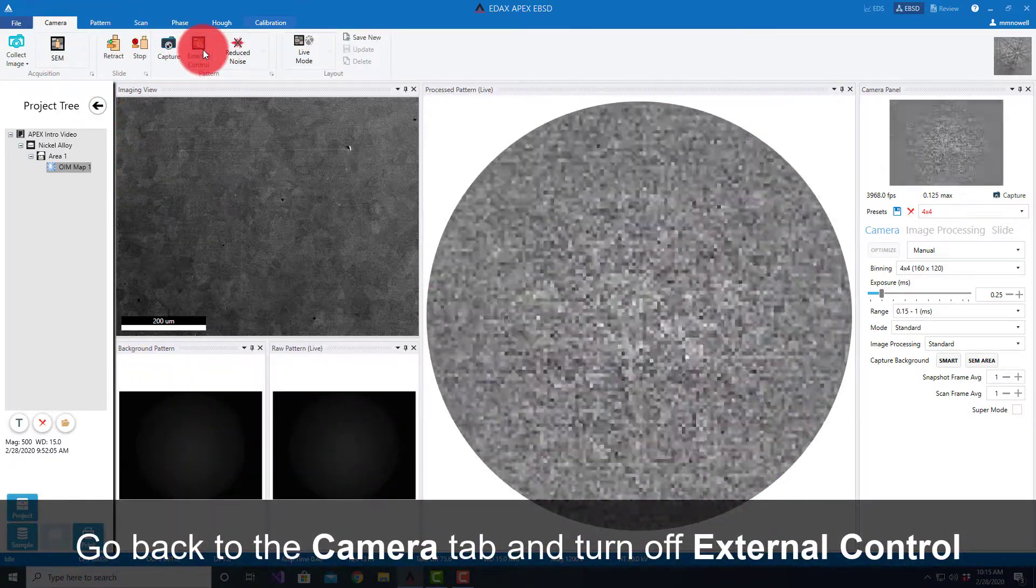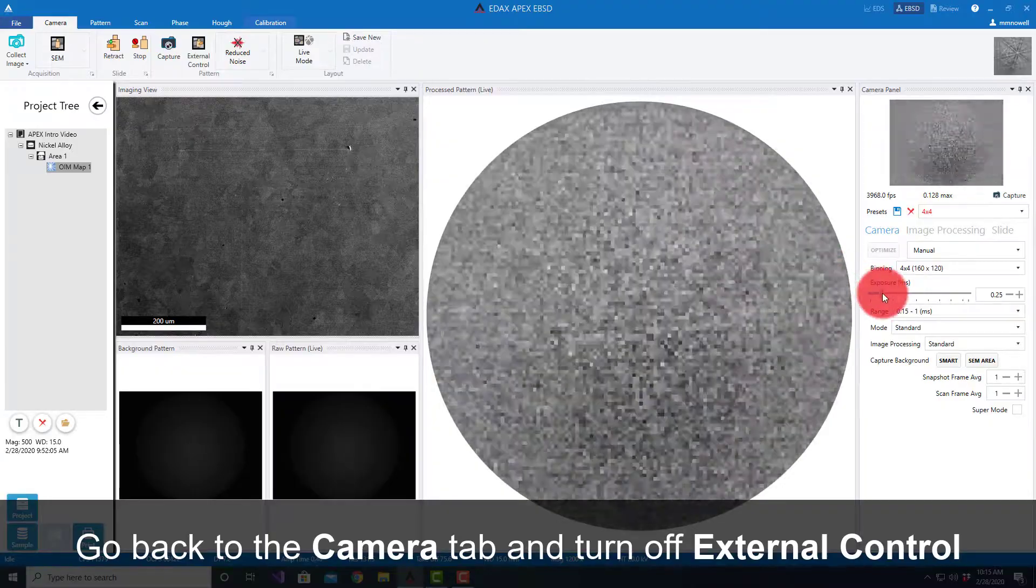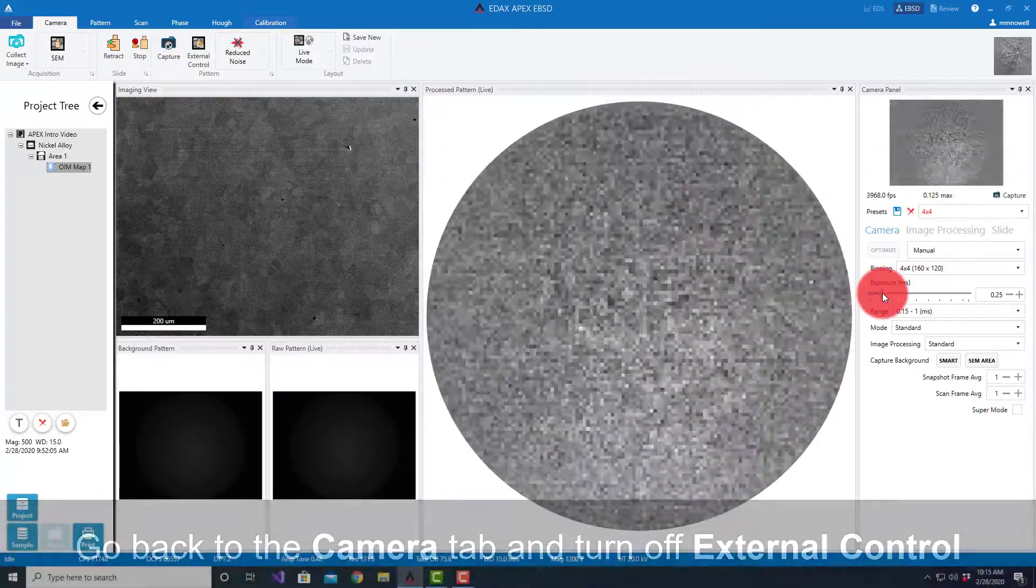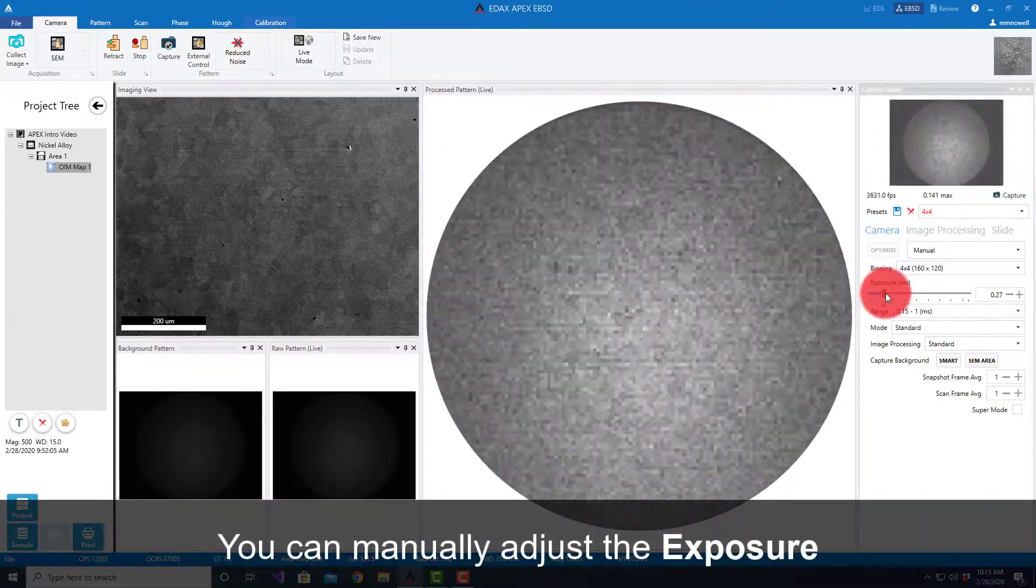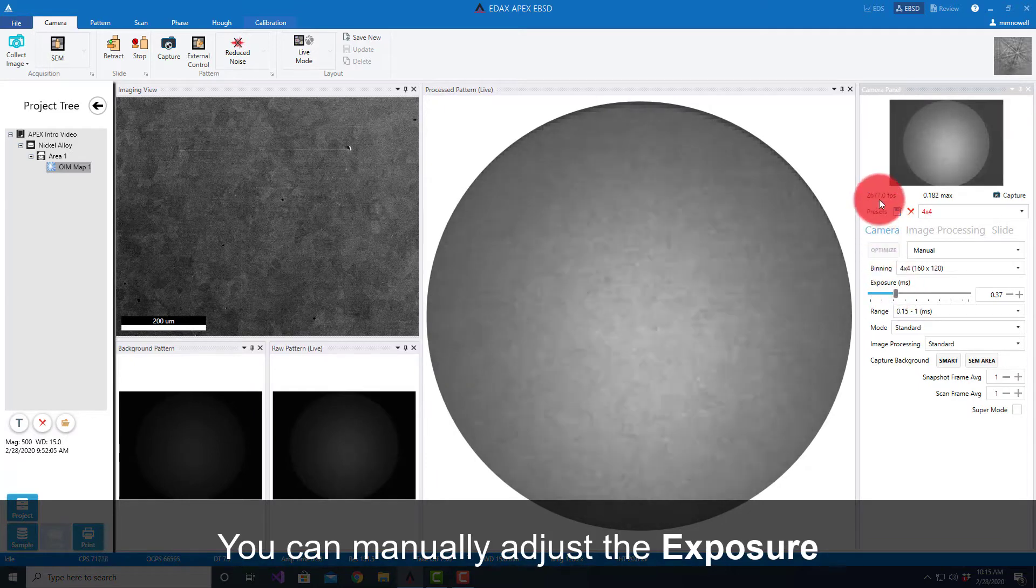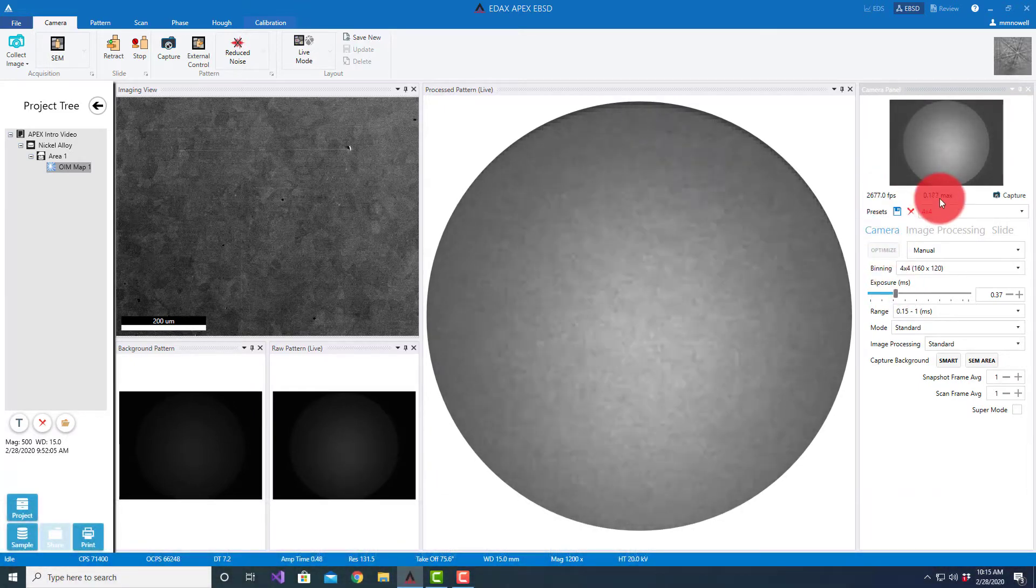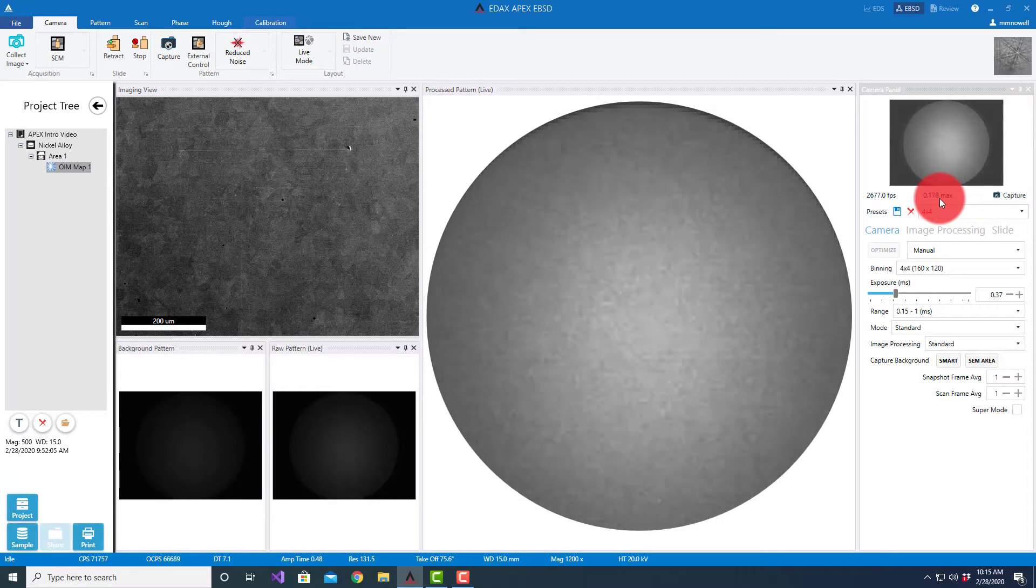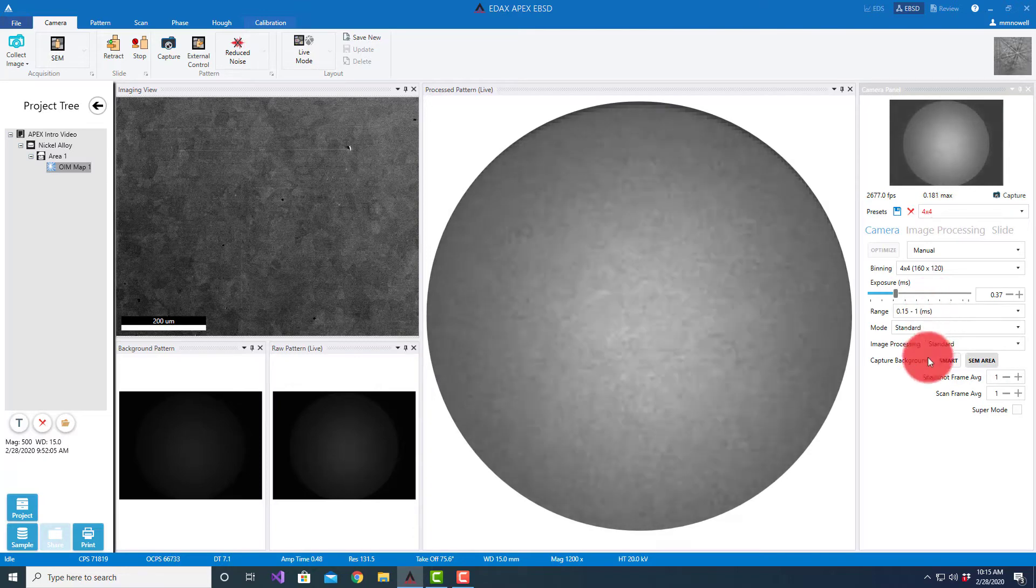I'll turn off external control. We also have the option of manually adjusting things. If I wanted to go a little bit slower, I can turn up the exposure time. As I increase exposure time, my frame rate decreases, my saturation level or intensity level increases. Once I'm in an area I'm happy with, I can capture background.